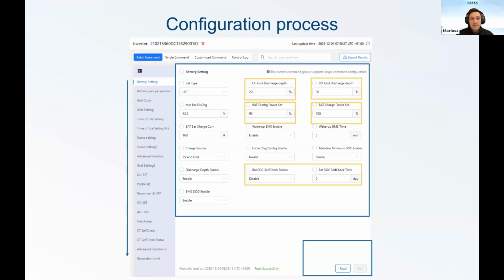Regarding the configuration process, we have some sections which we are going through. I just highlighted the most important settings, so let's say we skip the rest. If you want to make it clear and easy, and everything working without any special requirements, we can deal with those settings. The first is to set up the battery settings, like the on-grid discharge depth and the off-grid discharge depth. We can set up the battery discharge power or battery charge power. It's not so important. For example, if we have some kind of limitation, or if we want to work with a 0.25 C ratio for a longer cycle life, we can do it, but it's not so important.